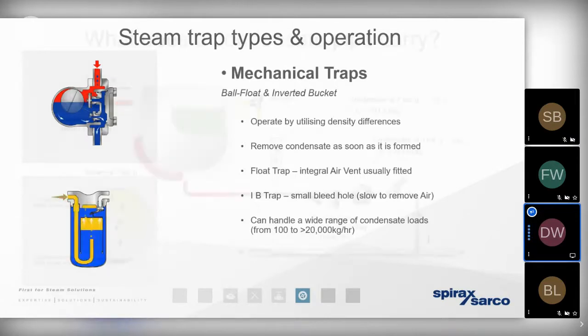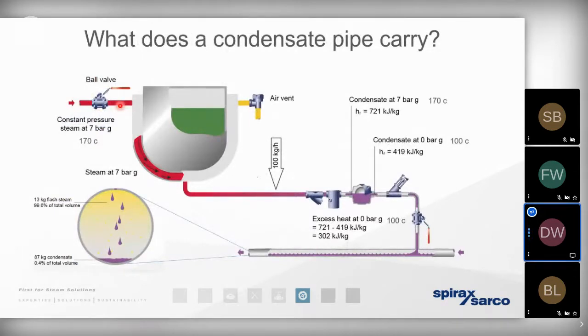So moving forwards, I just want to reiterate what condensate actually is and how we need to size the pipework between the process itself and the steam trap. So if we've got a process that is calling for 100 kilograms per hour of steam, we know that when steam gives up its heat energy and condenses, we're going to be left with the same mass of liquid condensate that needs to be removed. But remember that safety factor. It's good working practice to ensure that when the steam is bringing the process up to temperature from cold, we double that or maybe even triple it in certain cases. So it'd be good working practice to size the pipework at this point here for the fact that it may need to remove 200, maybe even 300 kilograms per hour of condensate.